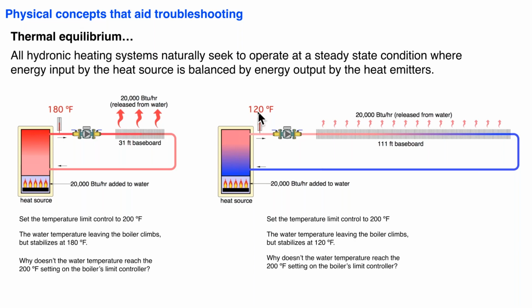The reason, again, is the system has found that natural balance point. It's found its thermal equilibrium between the rate of heat input and the rate of heat dissipation. So again, from a troubleshooting standpoint, understand that if a temperature isn't going higher just because you set a control setting higher, there's a reason for that. And typically the reason is it doesn't have to go higher in order to achieve a balance. And remember, every hydronic system is trying to find this balance, whether it's a really simple system like this or a complicated system.